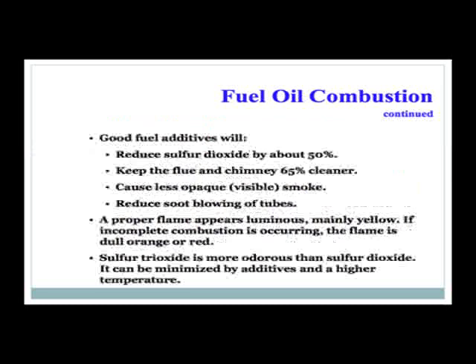Sulfuric acid will corrode steel rapidly and discolor brick and stone. Good fuel additives will reduce sulfur dioxide by about 50%, keep the flue and chimney 65% cleaner, cause less visible smoke, and reduce soot blowing of tubes. A proper flame appears luminous and mainly yellow. If there is incomplete combustion, the flame is a dull red or orange. Sulfur trioxide is more odorous than sulfur dioxide and can be minimized by additives and higher temperatures.